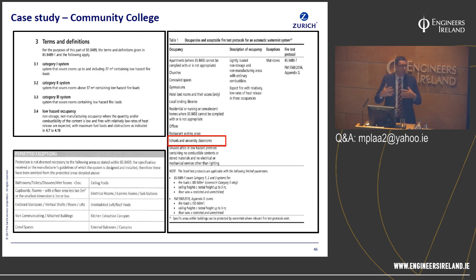So we're building a picture here of making something look better than it is and making it cheaper. But by digging a bit deeper, we can see the reason why it's cheaper and where it falls short of evidence. But part of the issue here, though, is that the standard is not great. Well, the standard is fine. The standard tells you what you can fit it in. So for me, if you haven't got test protocols for those other areas, you can't demonstrate it for those other areas. So perhaps in this case, water mist wasn't the right selection.